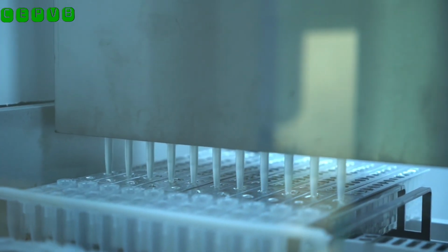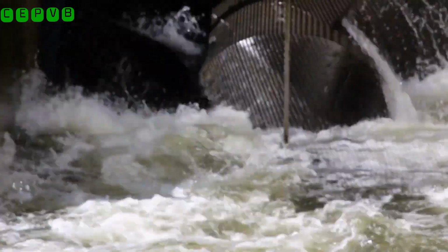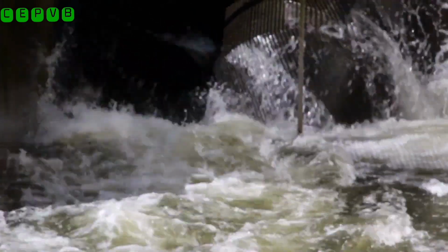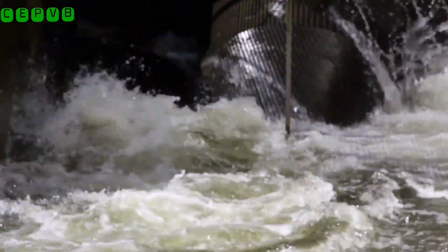This process starts off with a variety of mixing reactors, normally 1 or 2 reactors that add specific chemicals to take out all the finer particles in the water by combining them into heavier particles that settle out. The most commonly used coagulants are aluminum based, such as alum and polyaluminum chloride. Sometimes a slight pH adjustment will help clot the particles as well.